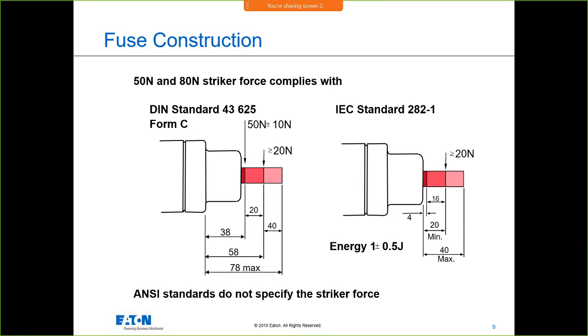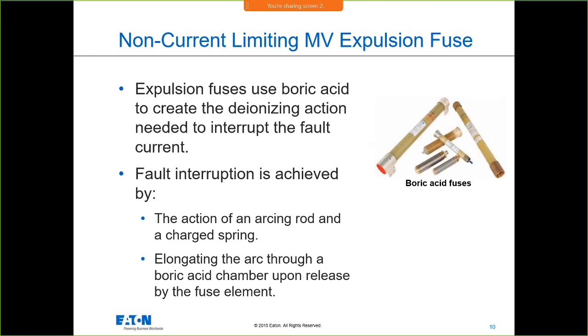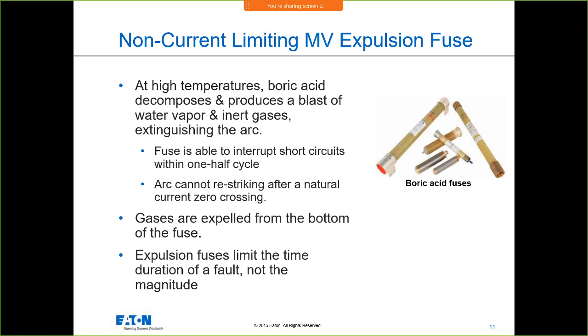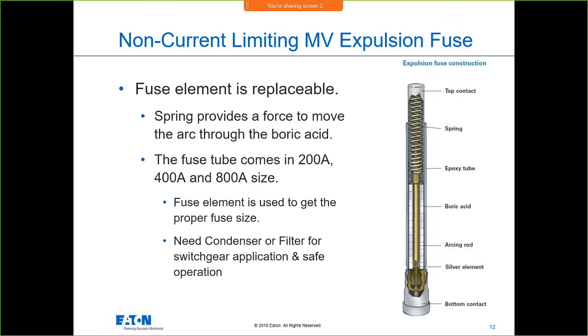Again, there are standards associated with how far it will protrude, but they don't talk about the striker force. Expulsion fuses use boric acid, and you can hear them go off when they go off. The boric acid decomposes, produces a blast of water vapor, and extinguishes the arc. It can't restrike. So again, they do their job. This is sort of how they operate.